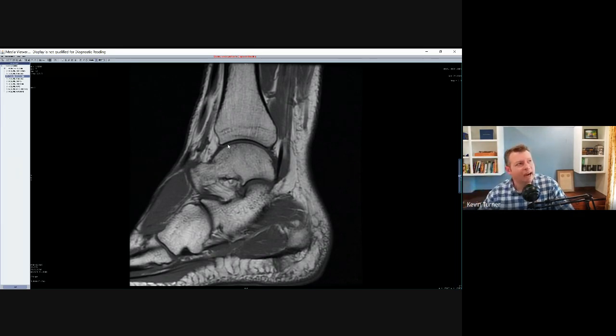So if I say, oh, well, the middle of K-space gives me the best contrast, so the middle of my image will have the best contrast. No, that's not true. K-space is nothing but numbers, right? You can't center your image better and get a better contrast in the middle. The contrast and SNR is the same throughout the image. It's just where the information is stored in K-space and then how it gets translated into an image. That doesn't mean when you set up your slices that something in the middle of the slice will be in the middle of K-space, which means the middle of your image will look the best. No. It does matter for where you're located when it comes to isocenter for your gradients, but the information that goes into K-space is nothing but numbers.